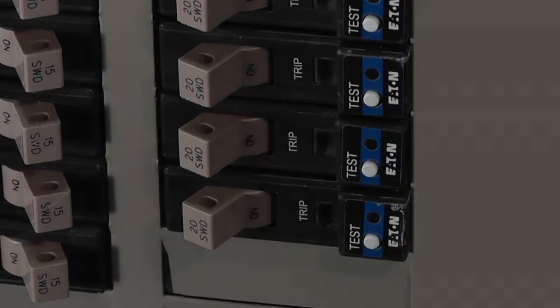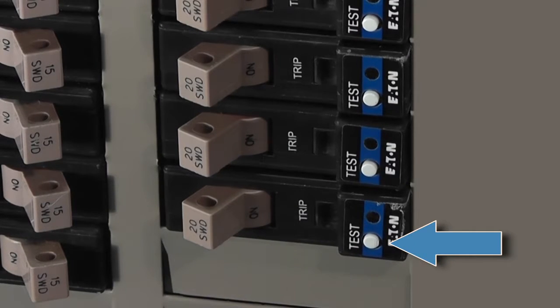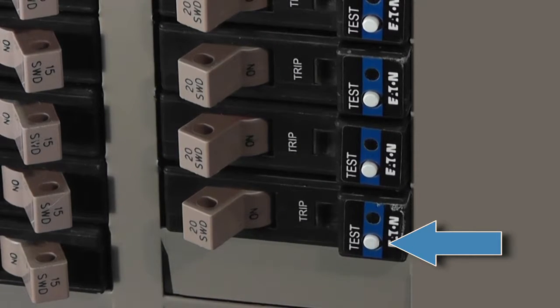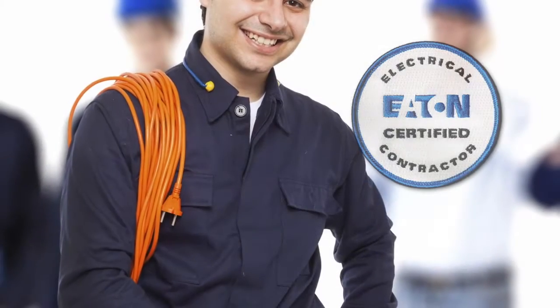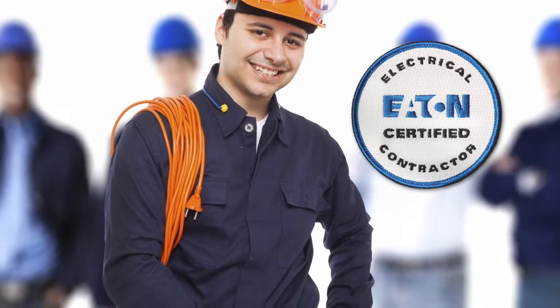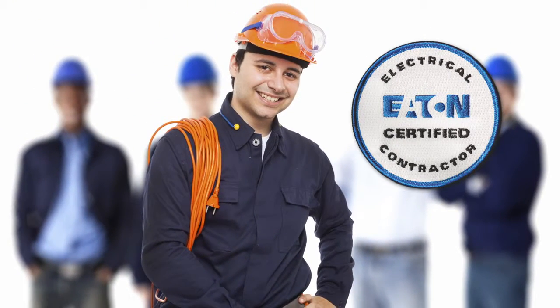AFCI devices are required to have a test button that ensures the device is working correctly. By pressing the test button, the device should trip, indicating it is working properly. If the device does not trip, contact a licensed electrician to have the device replaced. After you test the device, you will have to reset it.